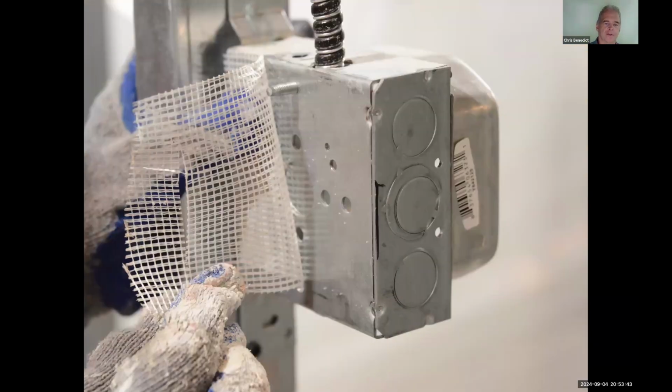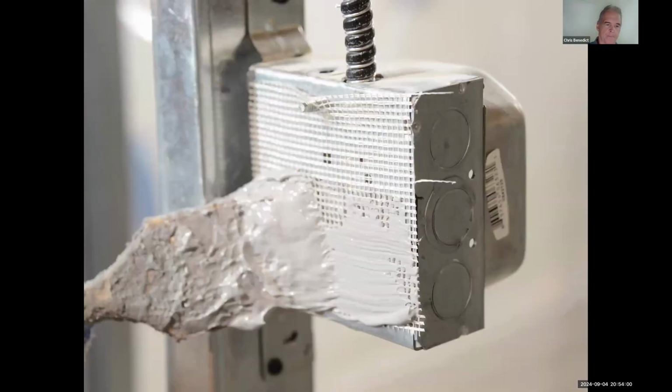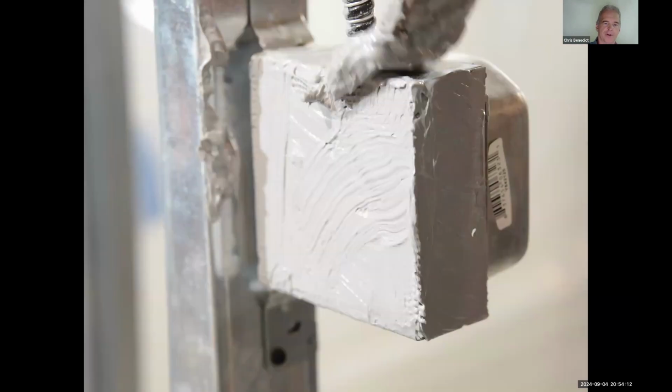So here's a standard electric box being made airtight. In New York, we still have metal boxes for all construction. There's no plastic boxes here yet. So that's fiberglass mesh. And then that's duct mastic. It comes water-based now. It doesn't stink up the job. And you put it on with a paintbrush. And there it is, all done. And it's all nice. So now you have an airtight electric box, so you don't have big air leaks to the box.